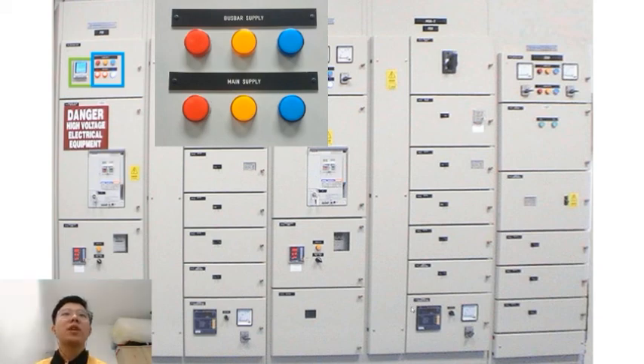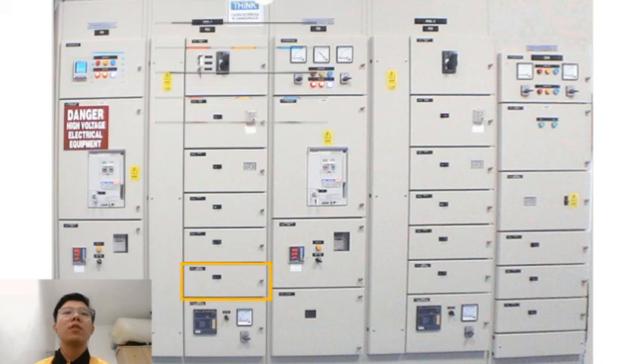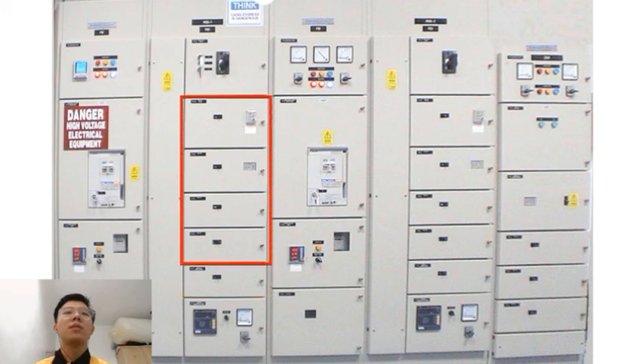After we check the indicator light of the bus bar supply and the voltage status, we will notify our consumer in order to turn on the supply. Once our consumer is ready, we will turn on the power factor capacitor, and after we turn it on, we will turn on the MCCBs one by one. After we have done everything, we will check the current status, and we will wait for a while until the system is in a stable condition.